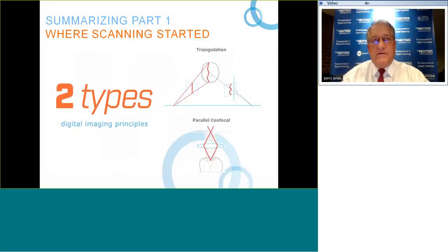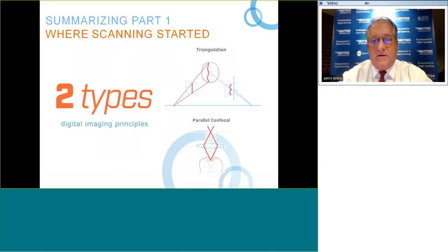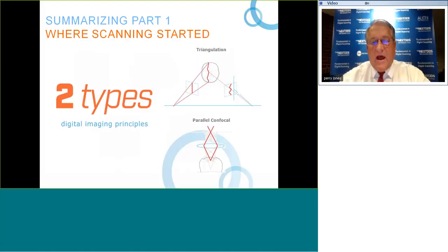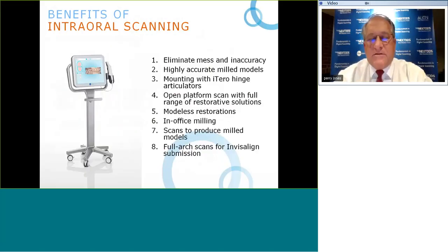With triangulation sampling, we had to use some sort of opaque dusting to create an optical field, eliminating reflections from things like large amalgam restorations — a cumbersome technique. That was not necessary with the parallel confocal system. Over time, the parallel confocal has proven to be an optimal system for highly accurate intraoral digital scanning. It does not require dusting or powdering — a huge advantage.